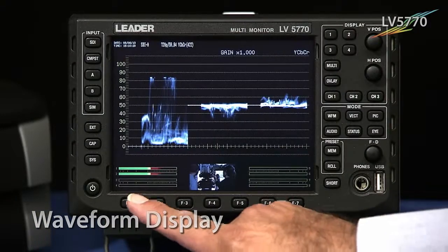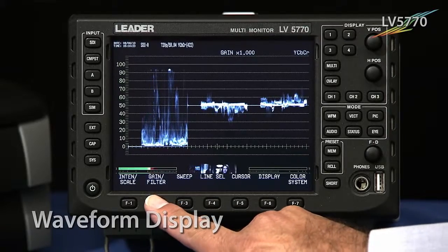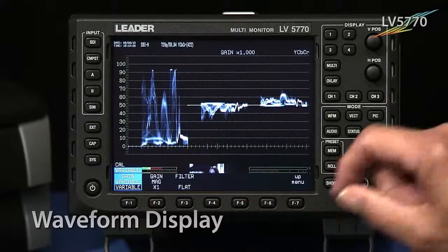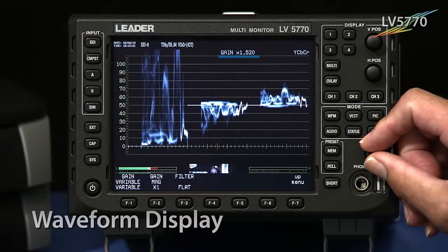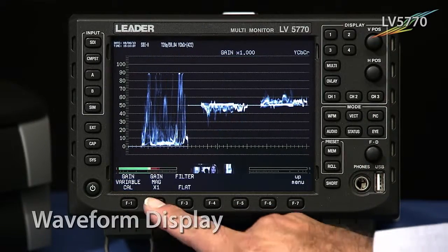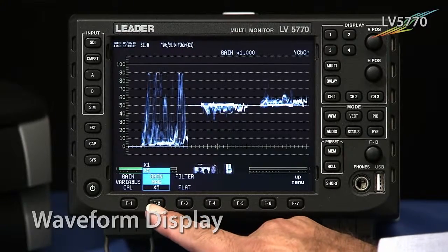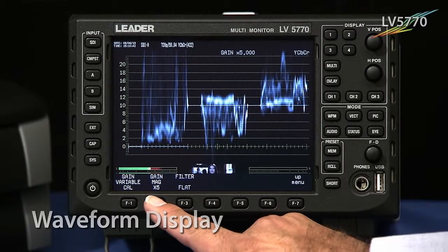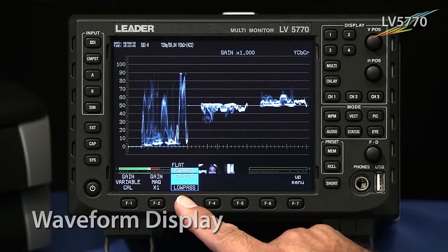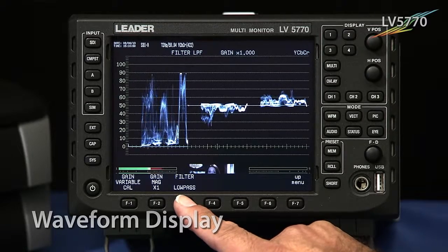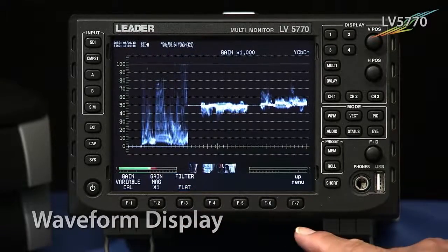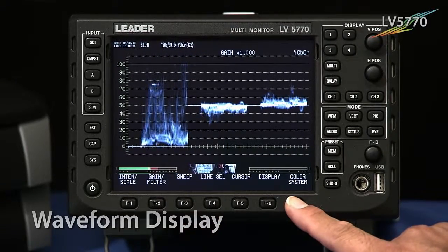As we move over to F2, the selection there happens to be gain and filters. This allows you to put the unit into a variable gain if you need to adjust the size and position of the waveform. F2 also allows you to magnify the waveform times five. F3 gives you the capability of adding a low-pass filter, which can sometimes help with items like interpolation where you've got additional detail that shouldn't be there. Hitting F7 again brings us back to the main menu.